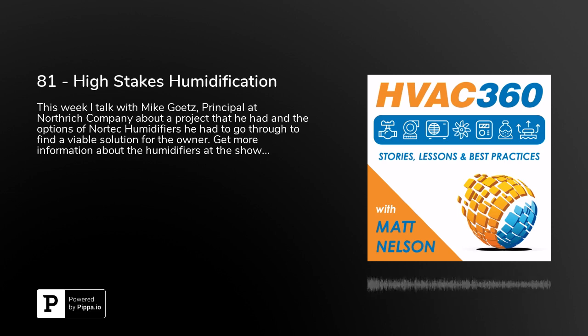So what would the flue be used for? That would be because it's a gas generator. Okay. It actually has a gas burner, and so you have to have a flue to go out. So the way the system is, you'd have to have multiple humidifiers, which wouldn't be a problem. It's just that there's no place to run the flues in this particular building because it's glass. You know, that's obviously the issue there.